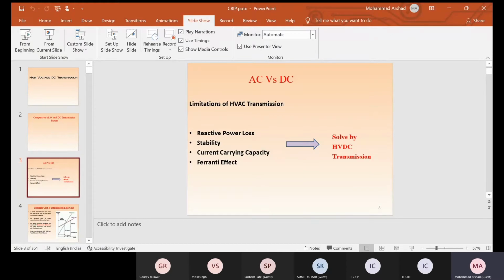For that we need to install many pumping stations for reactive power, so they can pump reactive power to the line so that we have a flat voltage profile. But what will happen? Your cost will increase and many complications will arise. That problem is solved by HVDC.